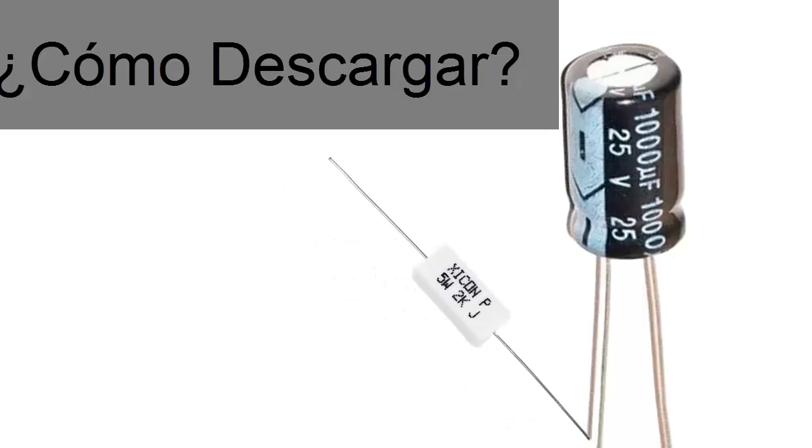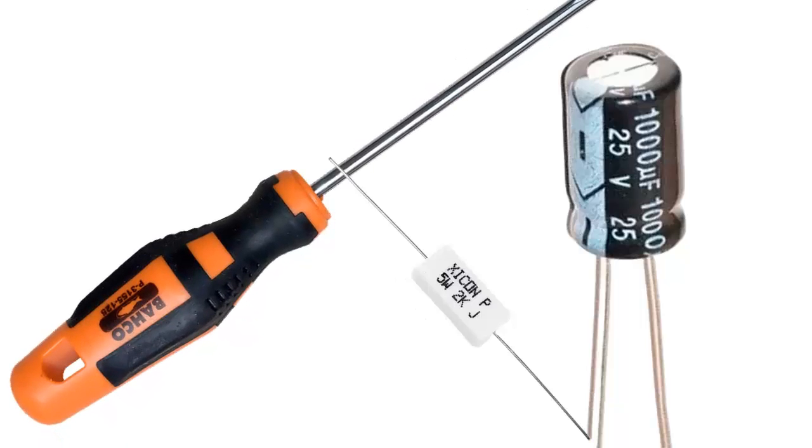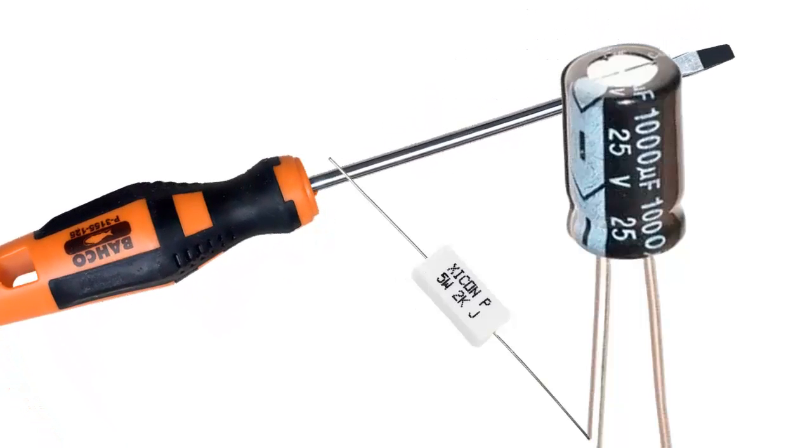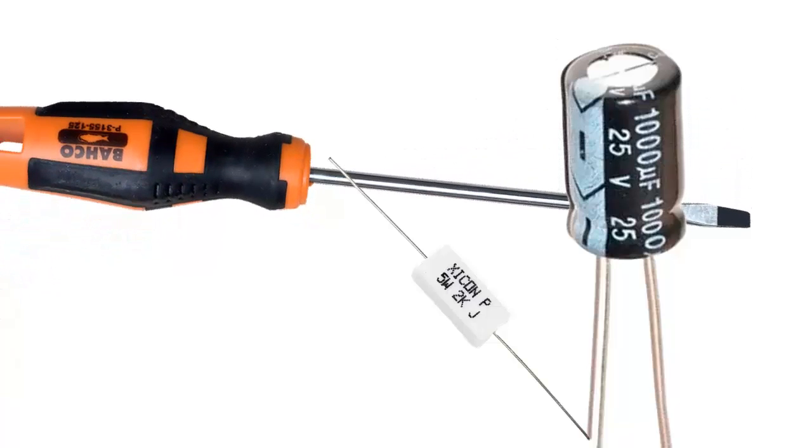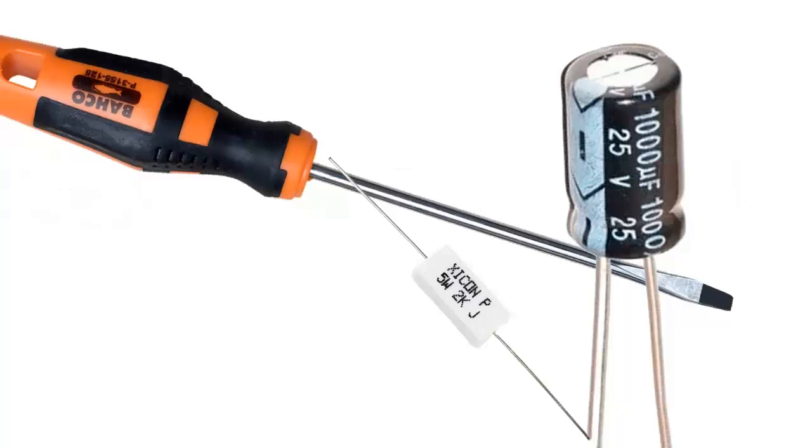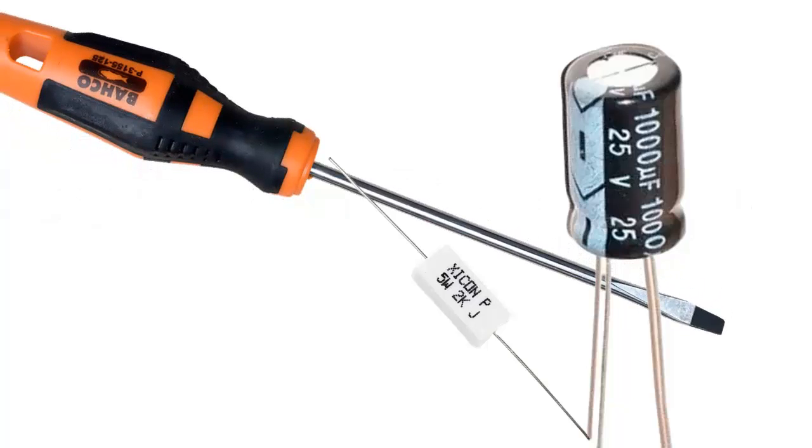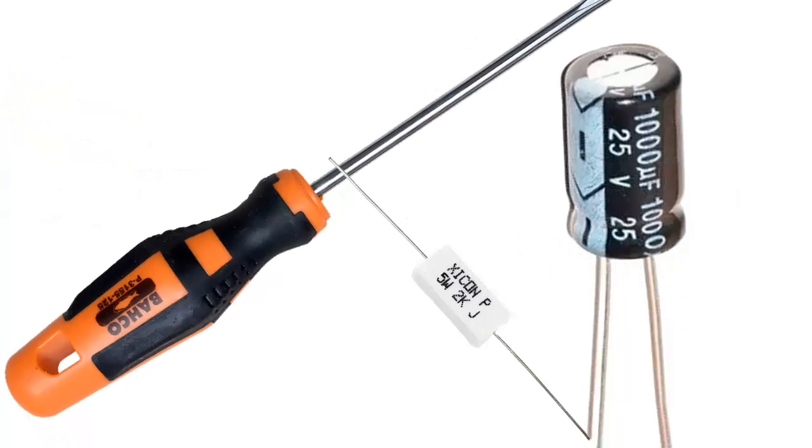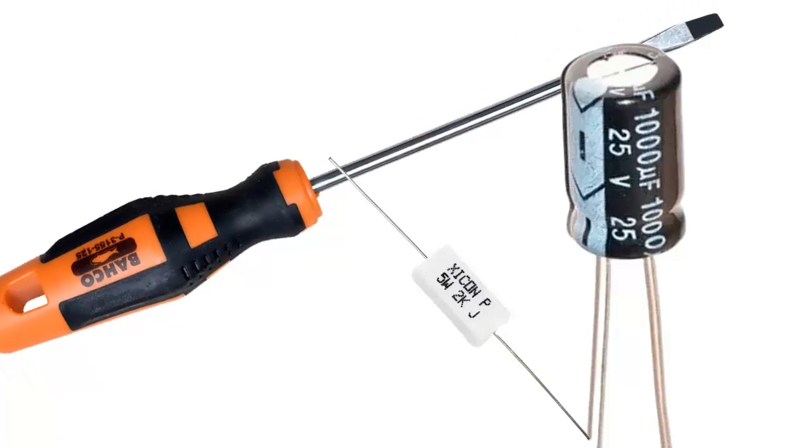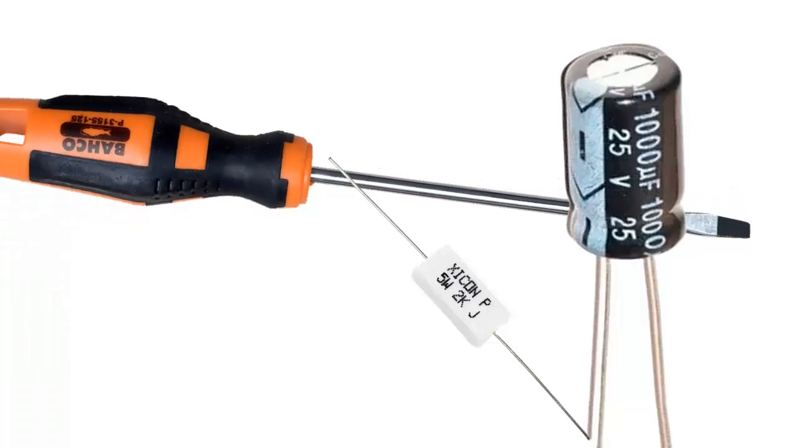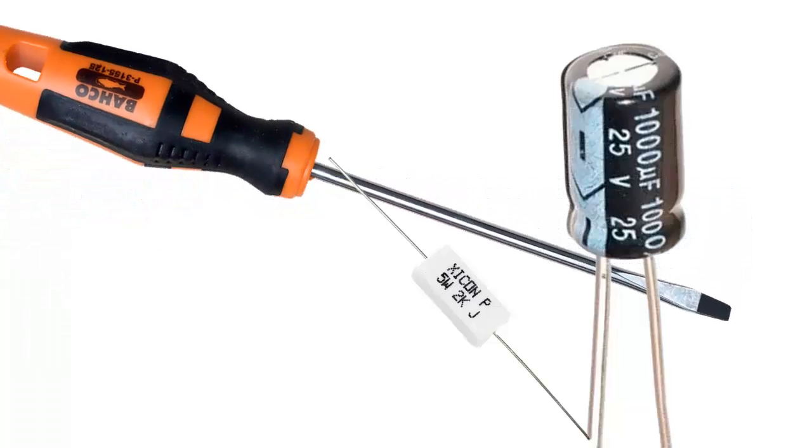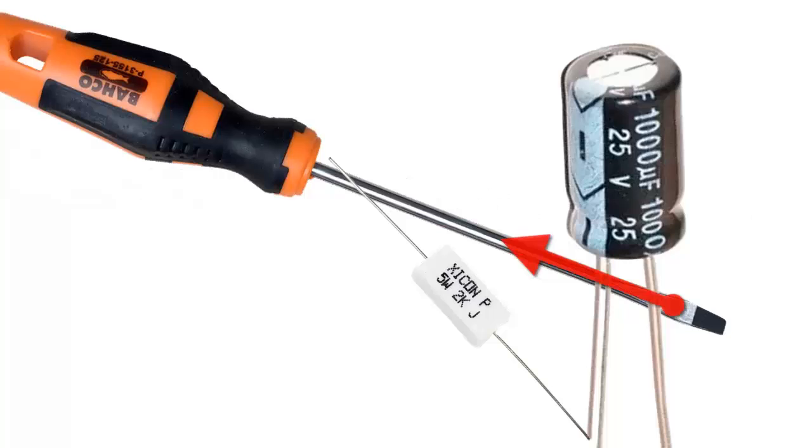To discharge capacitors on air conditioning electronic boards, it is recommended to use resistors in the range of 1 kilohm to 10 kilohms. For example, a 1 kilohm resistor provides a quick discharge but may cause a higher current flow. A 10 kilohm resistor provides a slower, more controlled discharge, minimizing the risk of sparks or damage to the capacitor.